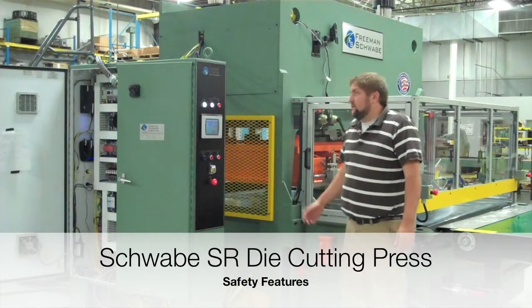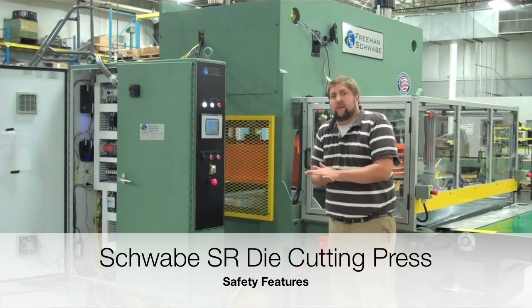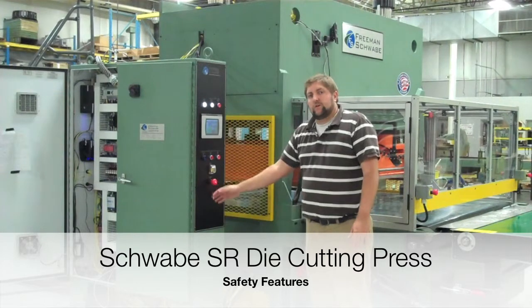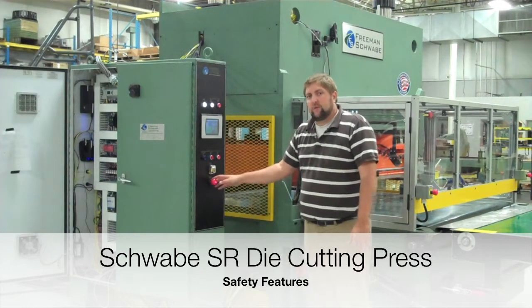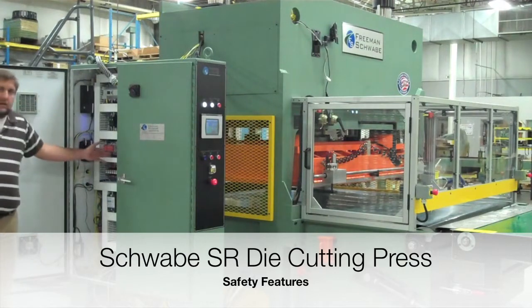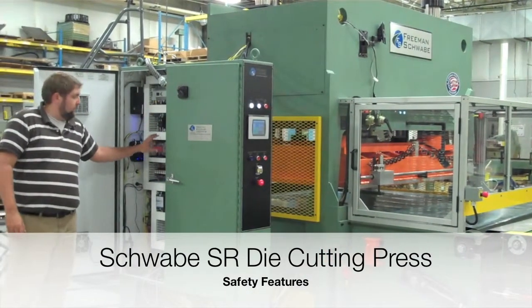Here again with the Freeman Schwabe SR press, straight ram design. We're going to talk about safety features of every SR that we ship out. Every machine comes with an OSHA certified safety stop circuit, which is wired to our safety relays. These safety relays force all the motor contactors and relays to fail in a safe manner.